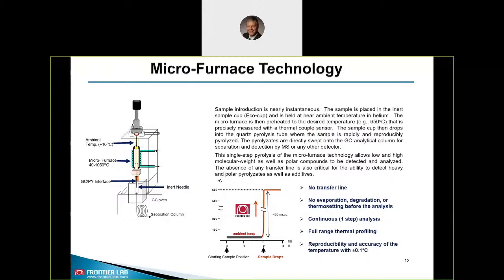How does the FrontierLab furnace technology work? You put your sample in the sample cup shown in yellow. The sample cup is kept at ambient temperature at the beginning. You heat up the furnace to the desired pyrolysis temperature, then release the sample cup and it falls free into the heated zone. The pyrolysates are directly swept onto the GC analytical column for separation and detection by MS or any other detectors. The benefits are: no transfer line, no degradation or thermosetting before the analysis, a one-step continuous analysis, a full range of thermal profiling, and high reproducibility and accuracy of temperature to 0.1 degree Celsius.